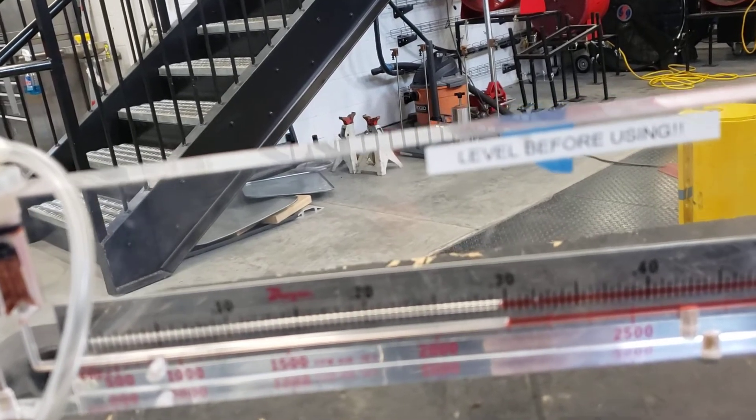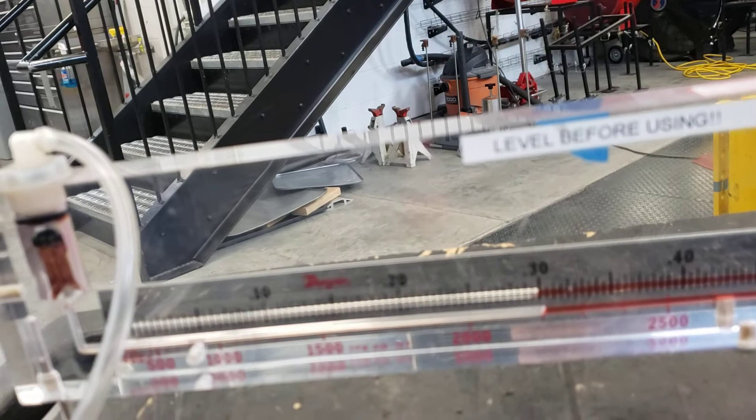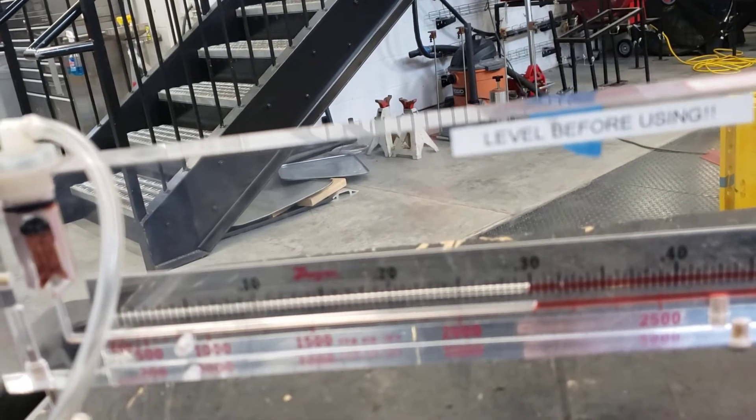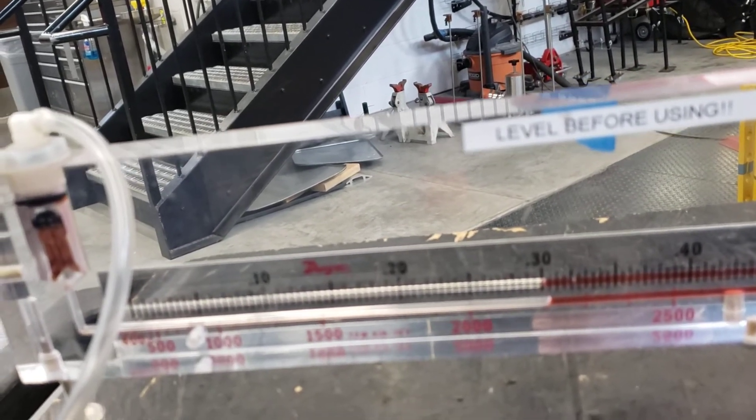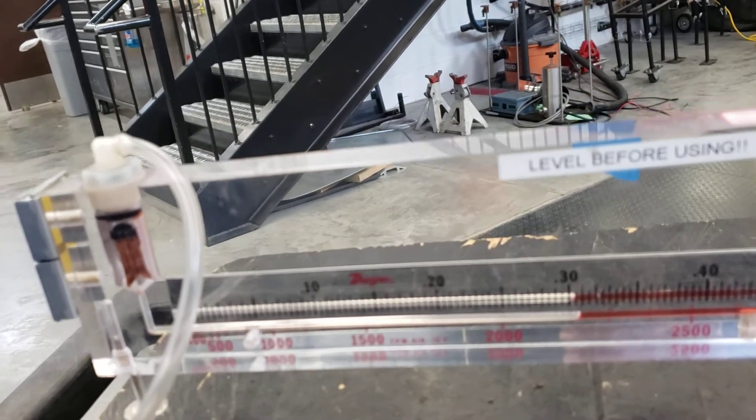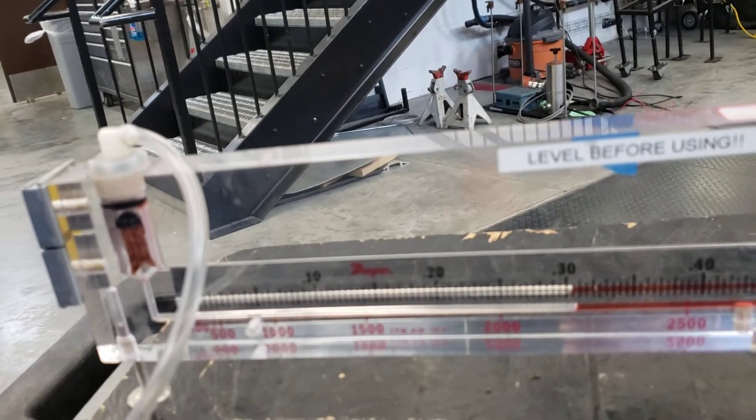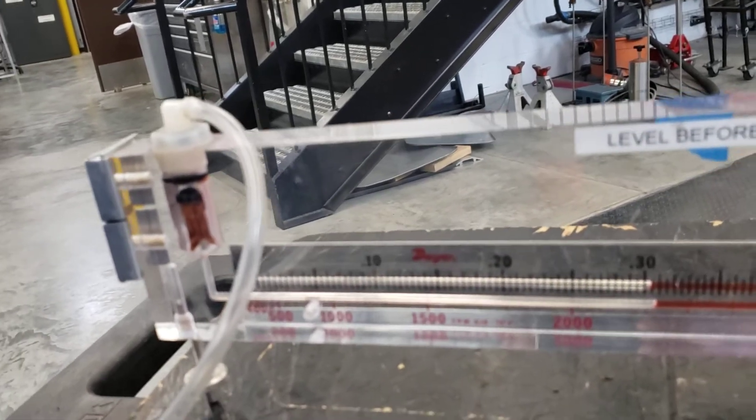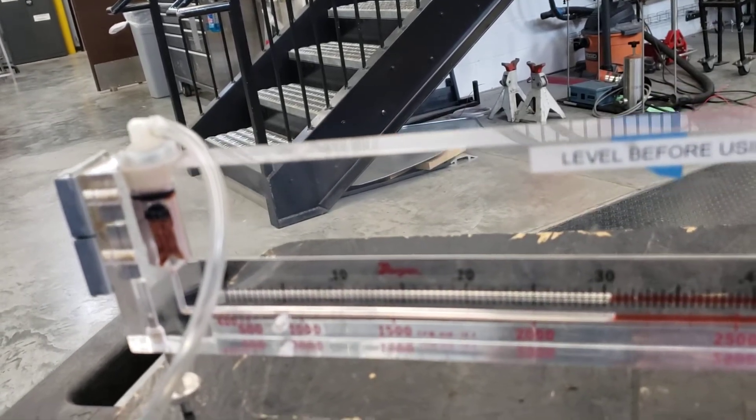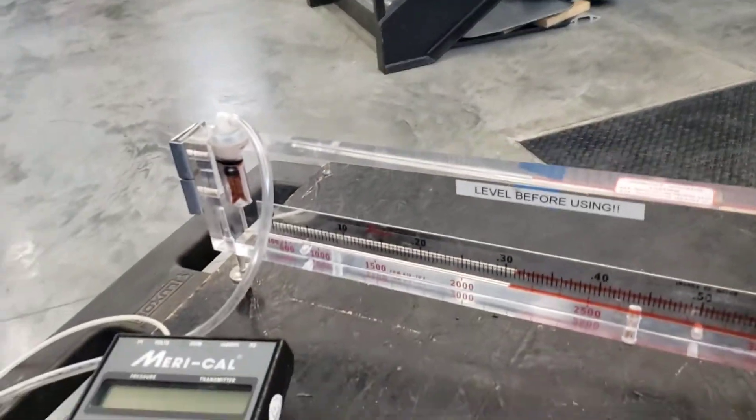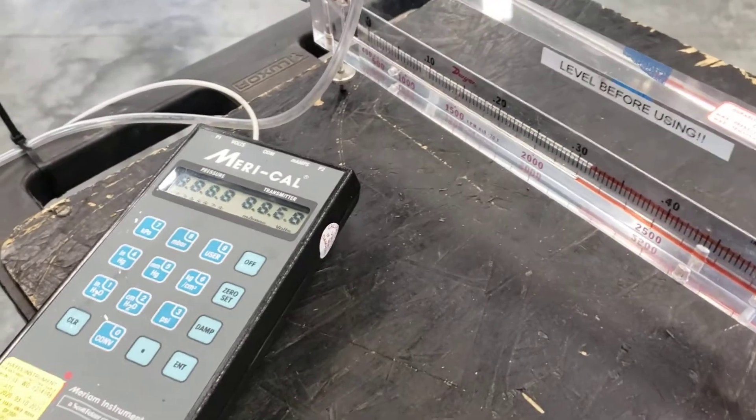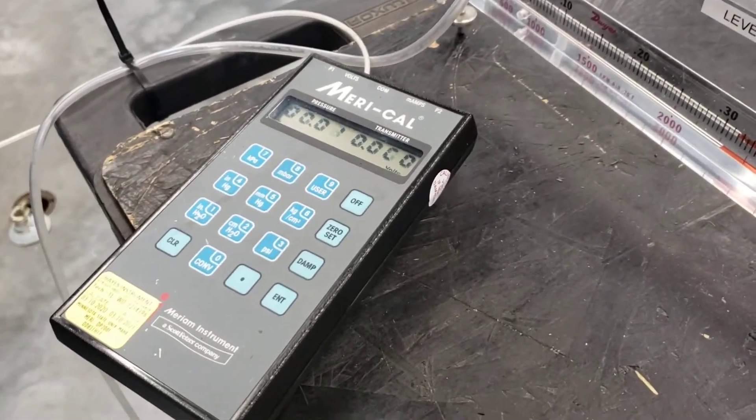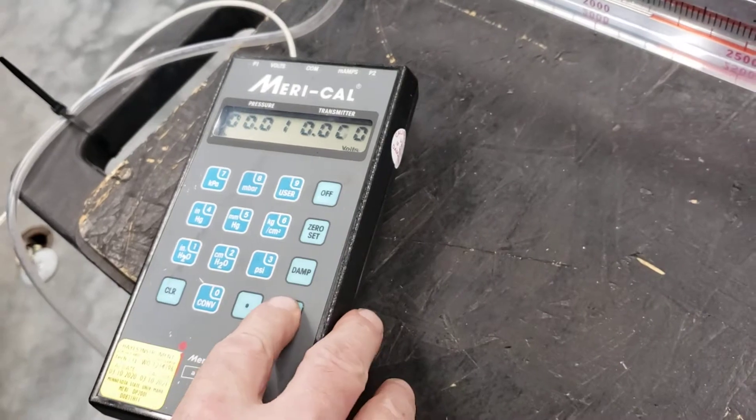It's getting slowly adjusted around 0.3 inches of water. It's about 0.31. Now we're going to show it using a digital one, so we'll disconnect the manometer. This is a digital manometer.